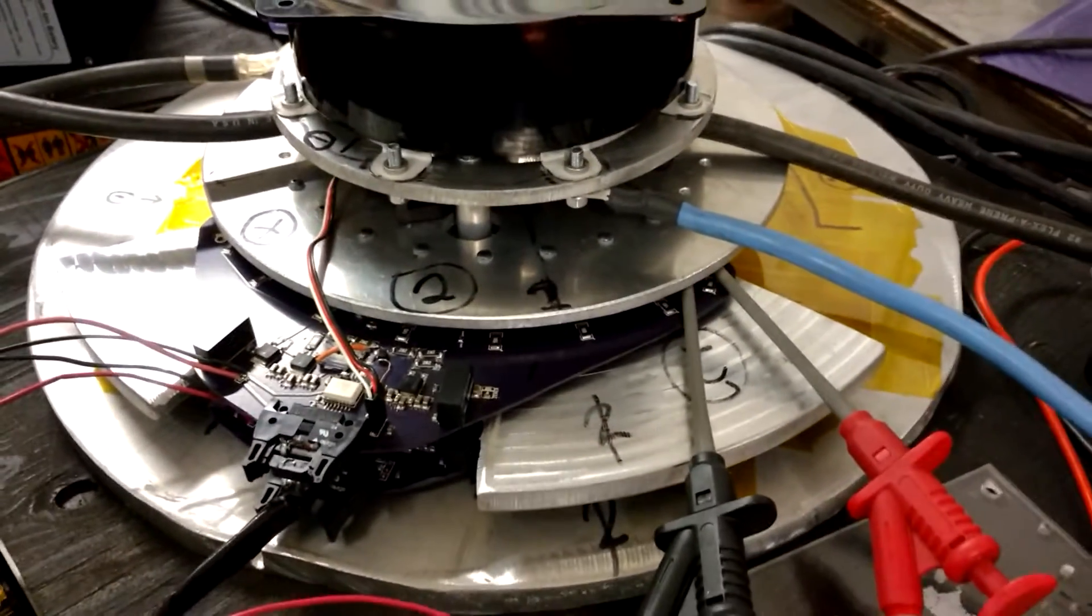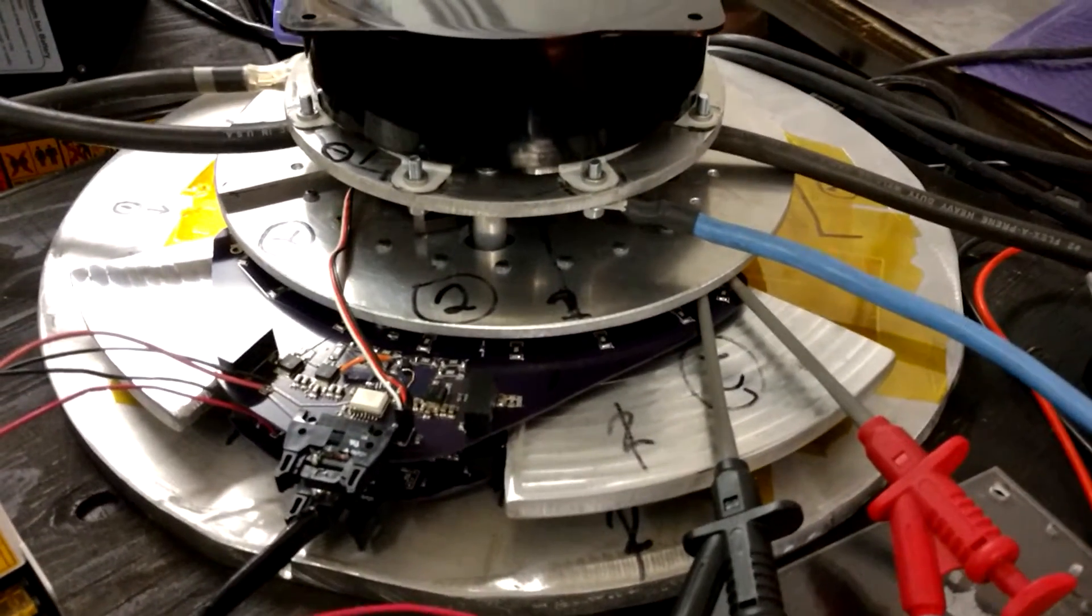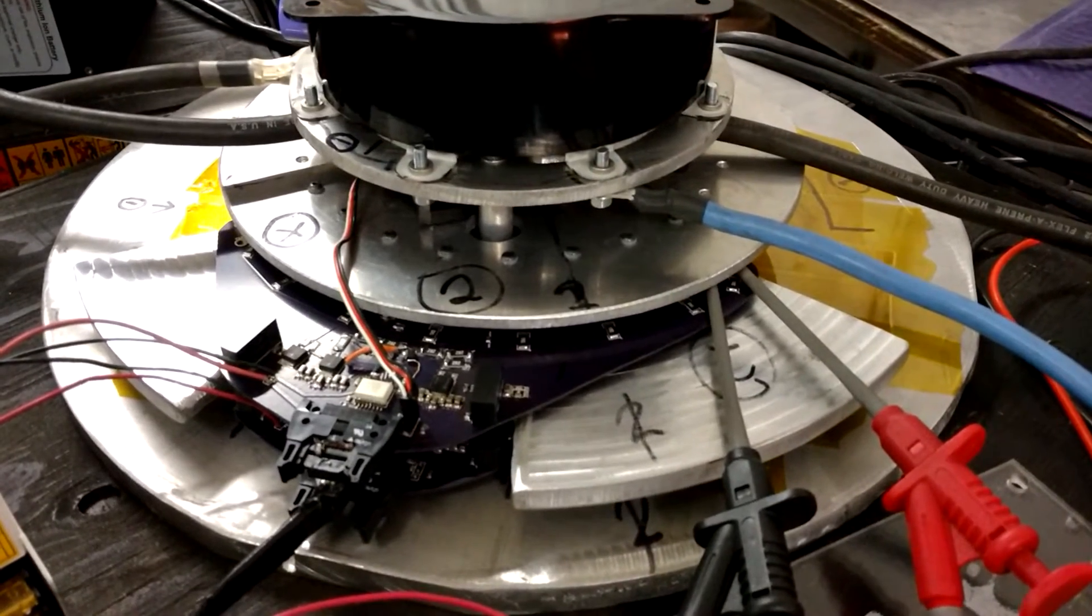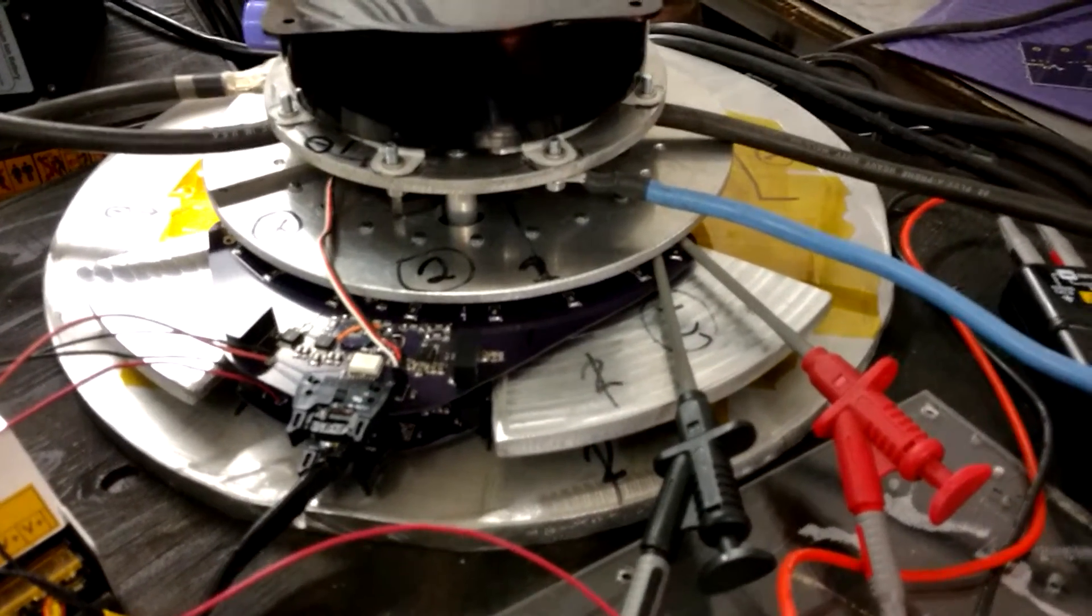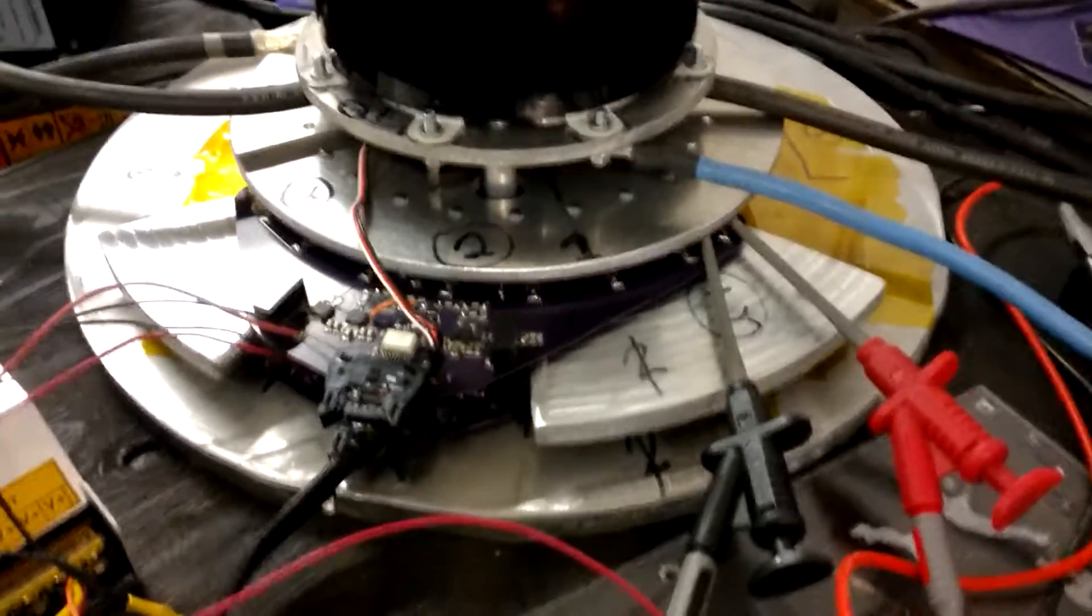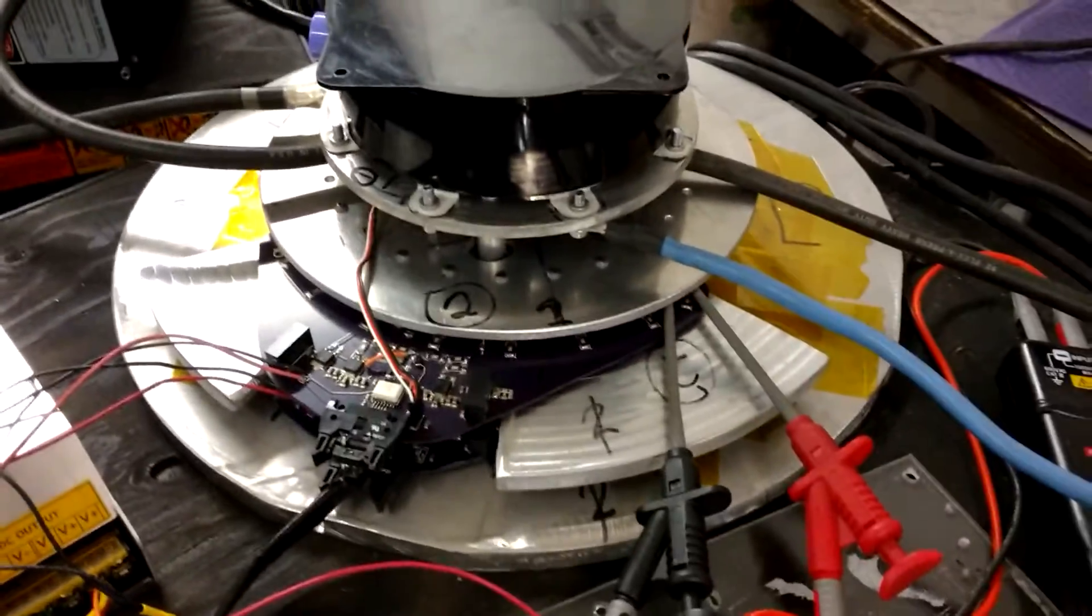So I think what I'm going to try and do in the meantime is I'm going to try and get some new current sensors. And then I'll, at least one current sensor to prove what actual amperage I'm running through this. I'll use that to set up the desaturation detection. And in the meantime, I'll try and get the other two sets of phases built up. So I can rebuild this thing as a full, ready-to-go, three-phase controller.